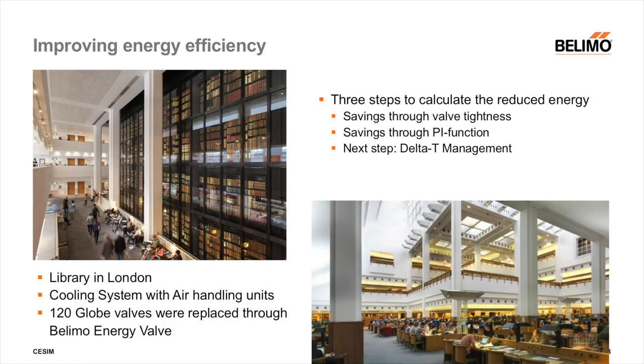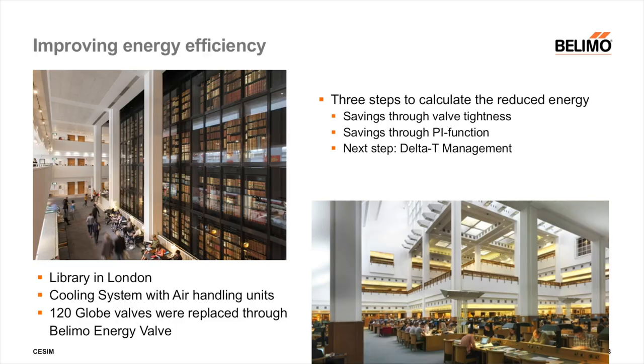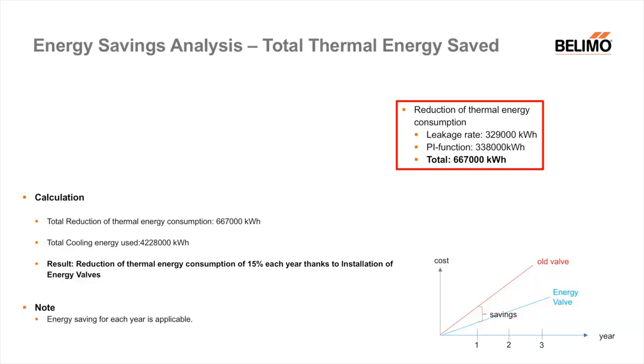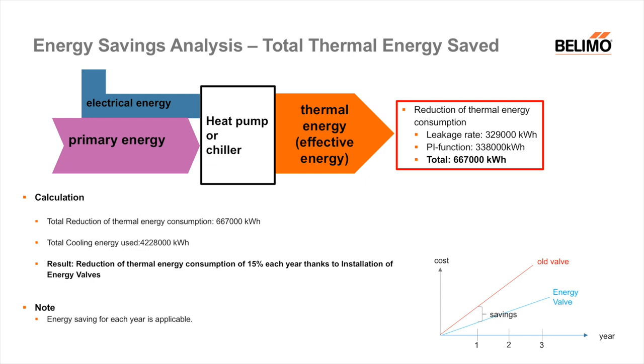We demonstrated the improvement of energy efficiency in a practical project in the UK. The building is a very large library with 120 air handling units and old globe valves. These 120 globe valves were replaced by 120 energy valves and we calculated the resulting energy savings. Thanks to the installation of the energy valve, annual savings in thermal energy were achieved through a better leakage rate and pressure-independent flow control. These total savings were about 15% every year in thermal energy, reducing thermal energy consumption by a total of 667,000 kWh.